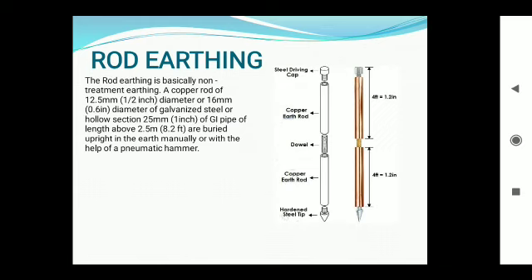The rod earthing is basically non-treatment earthing. A copper rod of 12.5 mm or half inch, it is not 1.2 inch, it is half inch diameter or 16 mm diameter, or galvanized steel or hollow section 25 mm of GI pipe of length 2.5 meter or 8.2 feet are buried upright in the earth manually or with the help of hammer.